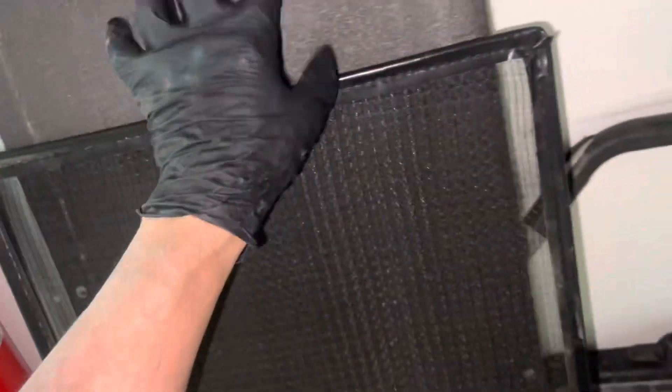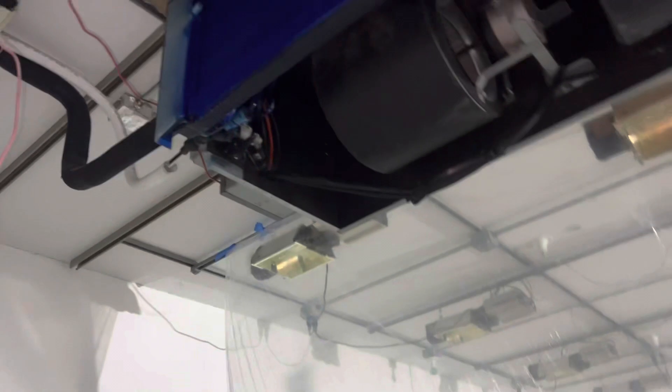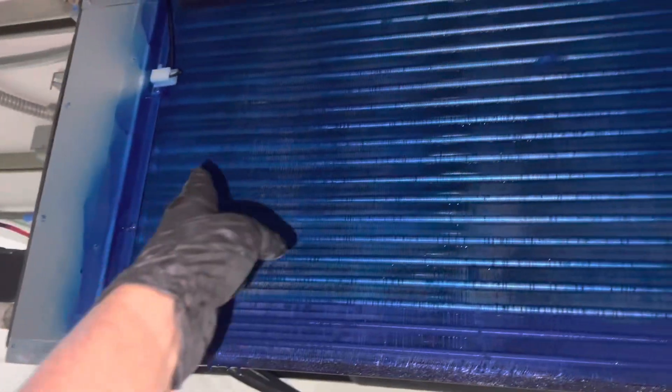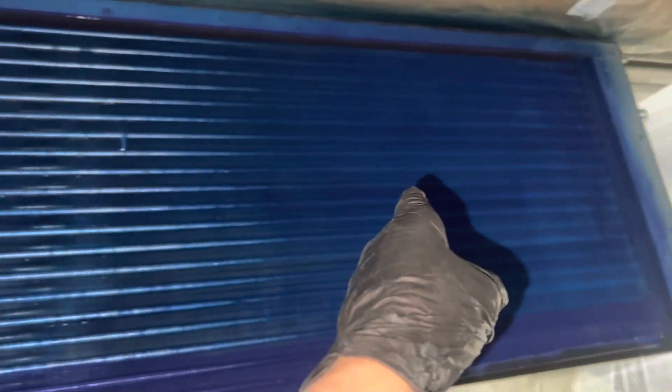We sterilized and used anti-fungicides on the insulation on the inside of the pans to kill any future fungus—it leaves a coating on there. Here's the outside of the coil with three coats of Gulf Coat Blue coil coater right there, and I have light coats on the top fins.